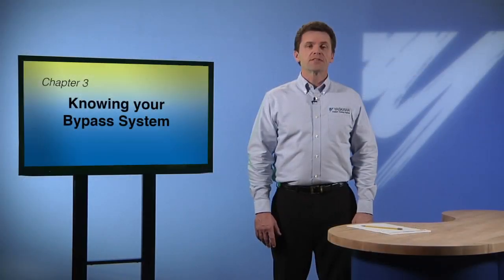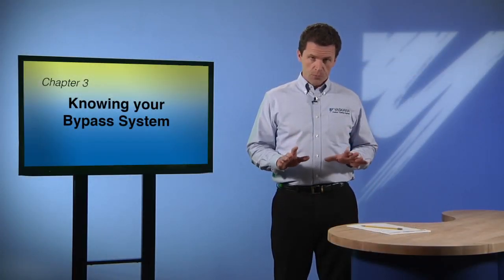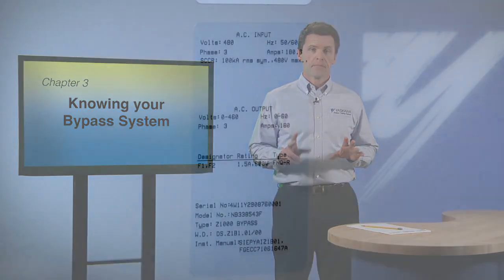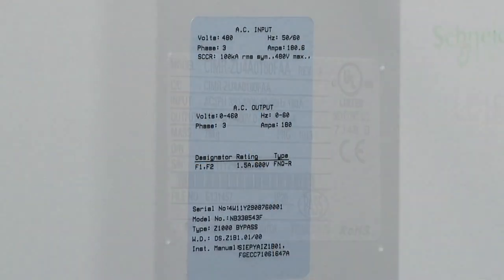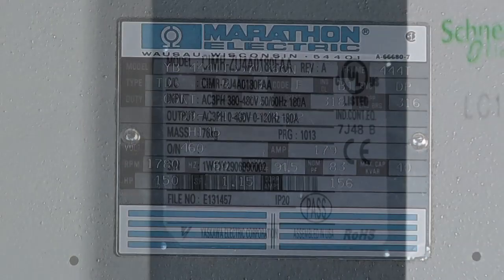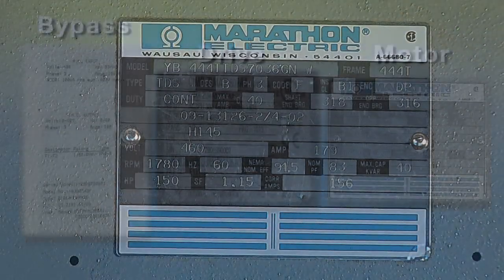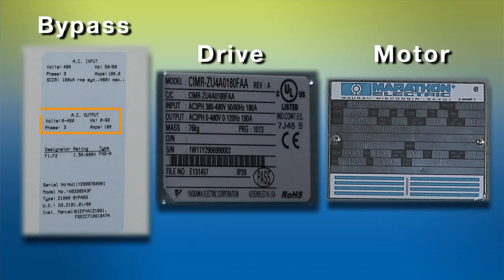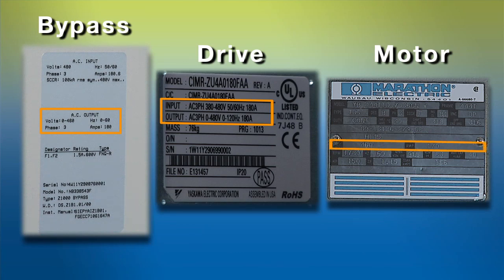We are almost ready to start setup, but before we do, we'll need to look at some nameplate information. We'll need to read the nameplates for our bypass, our drive, as well as for the motor that will be driven by our control. We'll look at the voltage rating for the bypass and the drive, then compare it to the voltage rating on the motor. We need to make sure that both the bypass and the drive are rated for the voltage that our motor requires. You'll want to write this information down for future reference and also write down the proper full load amp rating for the motor. You'll need the amp rating later.